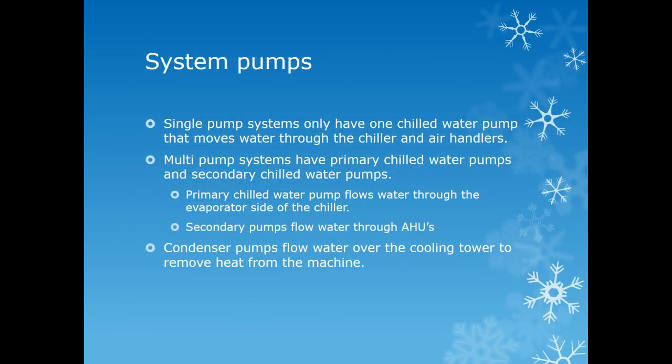Single pump systems only have one chilled water pump that moves water through the chiller and the air handlers. Multi-pump systems have primary chilled water pumps and secondary chilled water pumps. The primary chilled water pumps provide flow through the evaporator side of the chiller. The secondary chilled water pumps pull the water from the primary loop and distribute that water to the air handlers. The condenser pumps flow the water over the cooling tower to remove the heat from the machine.